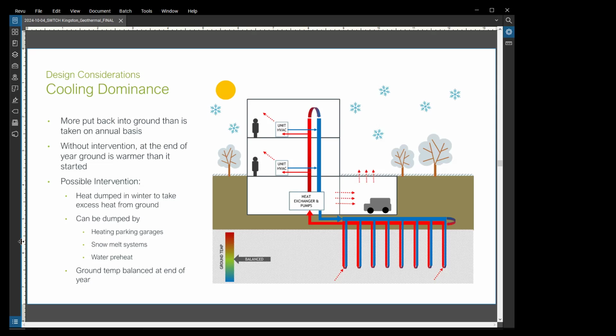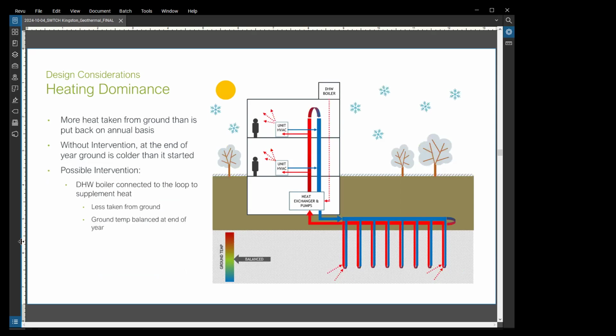There are a few easy fixes and a few more design related fixes to balance that out. The first easy fix is to connect your loop to your domestic hot water. Anytime your field temperature gets a little too low, you inject some hot water into it from your domestic hot water system. It's a great solution, it's on demand, it's simple, and it employs practices that construction teams are generally familiar with. The downside is most domestic hot water is connected to natural gas boilers, so in terms of carbon reduction it doesn't really help the situation.